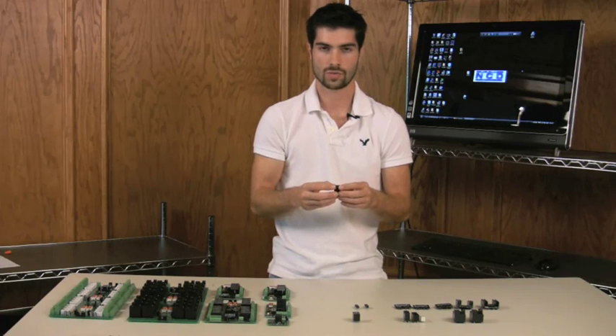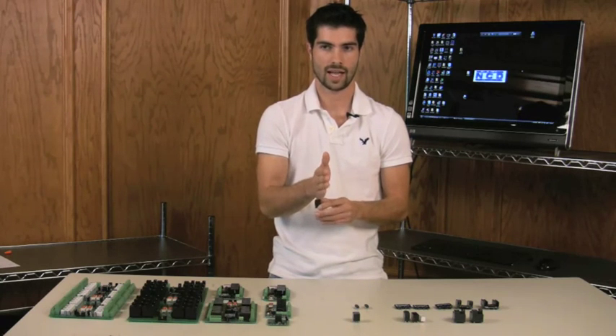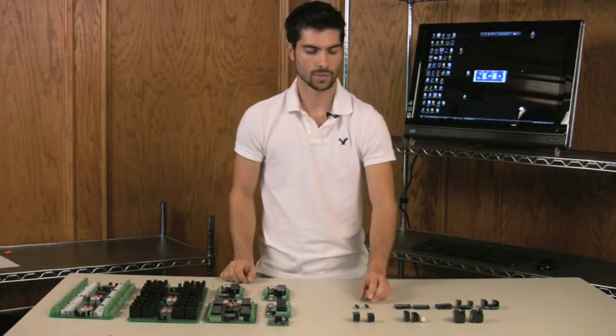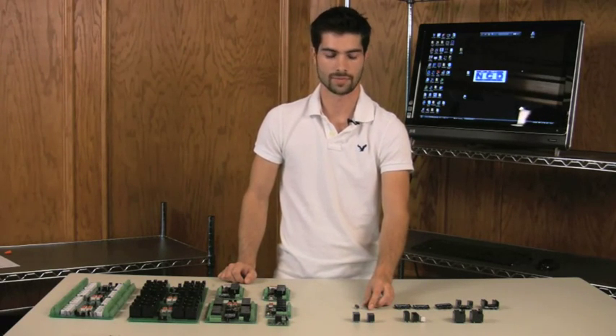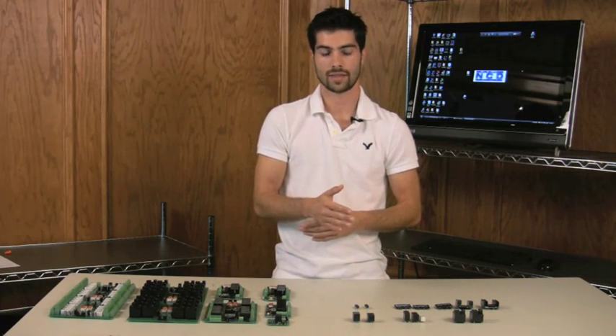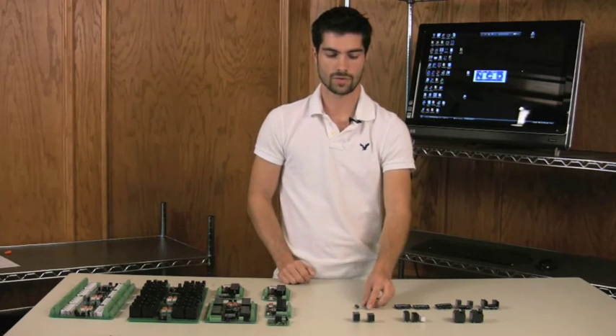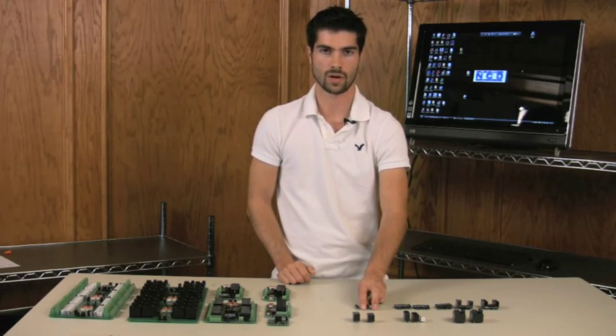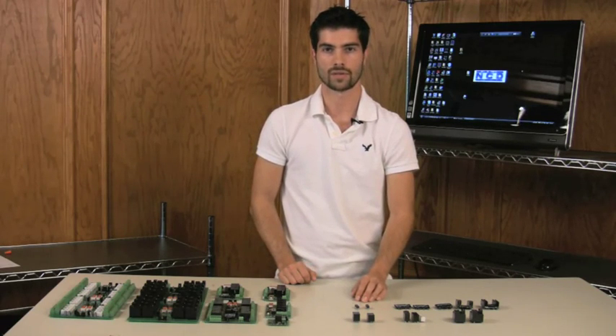So you can actually run two outputs out of this to two different devices. This doesn't have a neutral, so it means it's either connected to the normally open or the normally closed, one or the other. And we also have some relays that are single pole, single throw, meaning it's either in neutral, meaning it's connected to nothing, or whenever you energize it, it's going to connect to the normally open. So you can't make two output connections to these relays. You can only make one, which sometimes works really well for different applications.